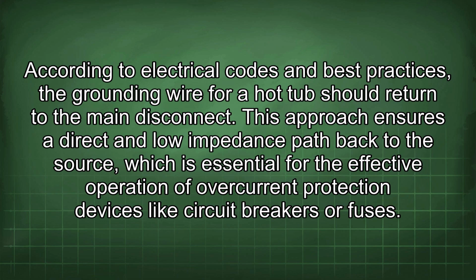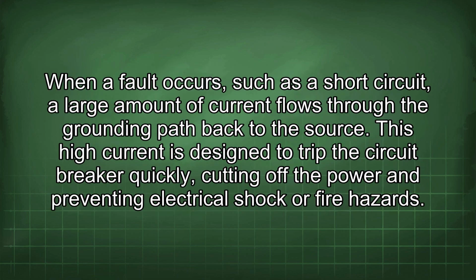This approach ensures a direct and low impedance path back to the source, which is essential for the effective operation of overcurrent protection devices like circuit breakers or fuses. When a fault occurs, such as a short circuit, a large amount of current flows through the grounding path back to the source. This high current is designed to trip the circuit breaker quickly, cutting off the power and preventing electrical shock or fire hazards.